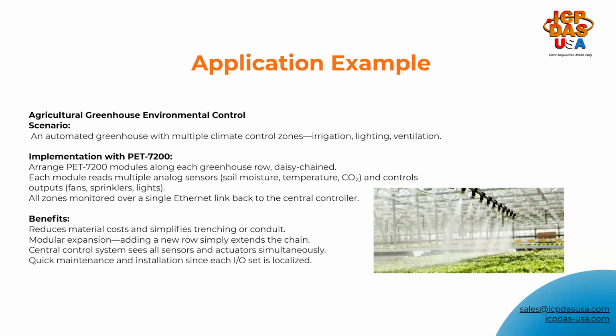Lower installation costs because you reduce wiring, trenching, and conduit runs. Scalability: if you need a new row, just extend the daisy chain with another PET-7200 module. Unified visibility: the central control system monitors every sensor and actuator simultaneously. And faster maintenance: since each I/O set is localized, technicians can easily pinpoint and service issues right at the row.